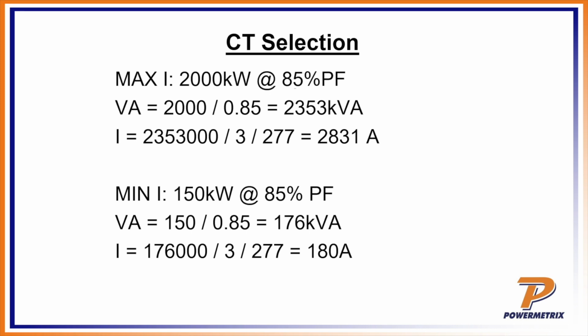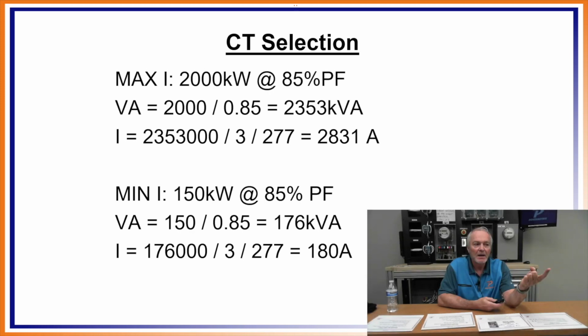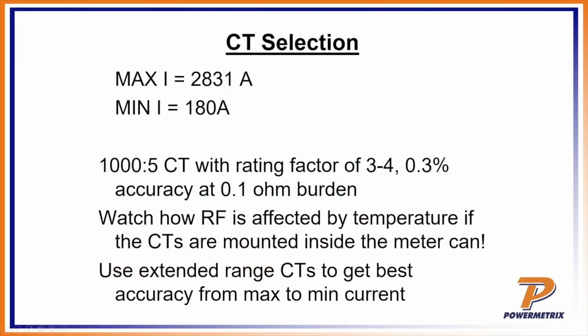CT selection, here we go, that max min, right? So the max we said was 2831. You can see up top we calculated that. So what about the min? Okay, so we do the same calculations for the min and we come up with 180 amps. So I'm ranging all the way from a min of 180 amps all the way up to 2831 on the max. Okay? So 1,000 to 5 CT with a rating factor of 3 to 4, 0.3% accuracy at 0.1 ohm burden.